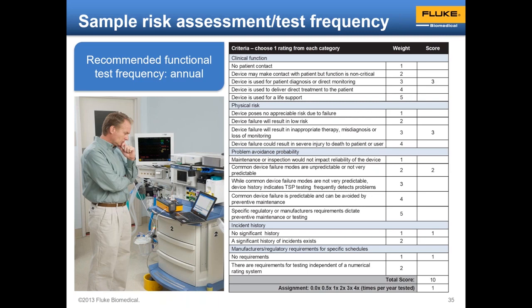We still will do the incoming inspection testing, all right? In addition to that, we will still test the patient monitor after any repair, right? So let's roll back for a minute and let's say, what if I had to send the patient monitor away from the hospital biomed department for that repair? Well, then it's going to come back into the hospital and we will do an incoming inspection. So we'll have that electrical safety test after we receive it back from whoever repaired it for us. We should do another electrical safety test. If we do the repair, then we must test after the repair to be sure that we made this patient monitor safe for the patient to be connected to it. You opened the patient monitor up and you replaced something.